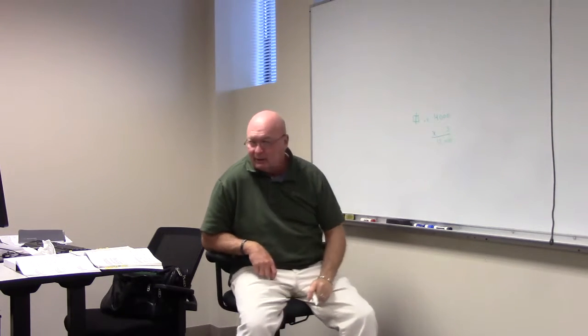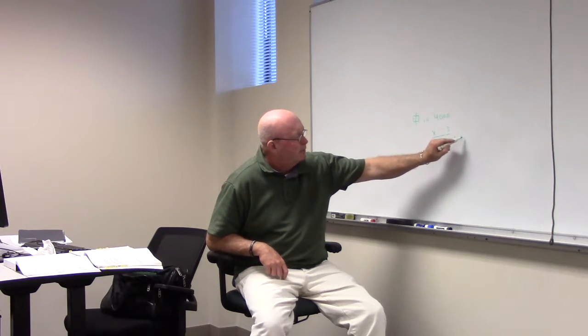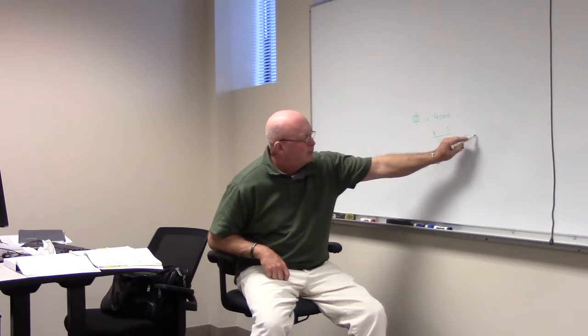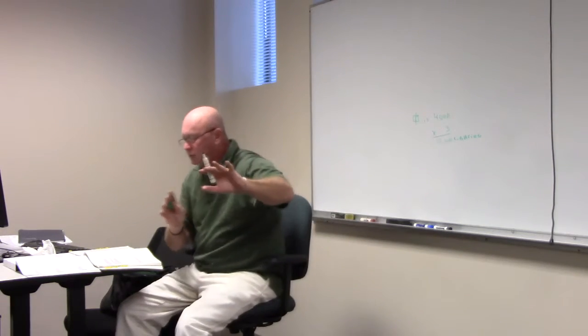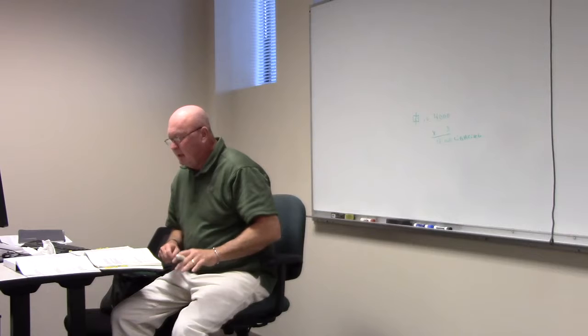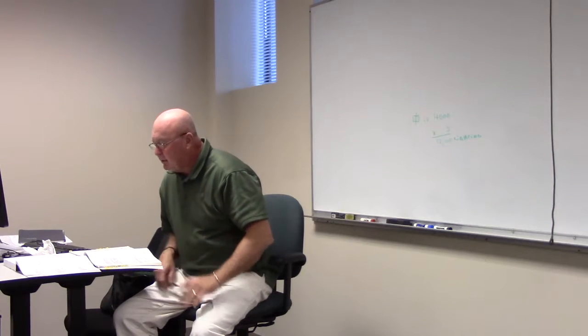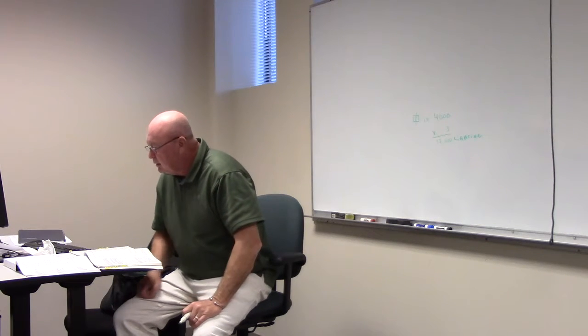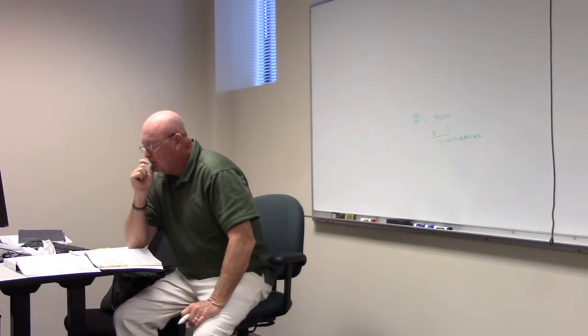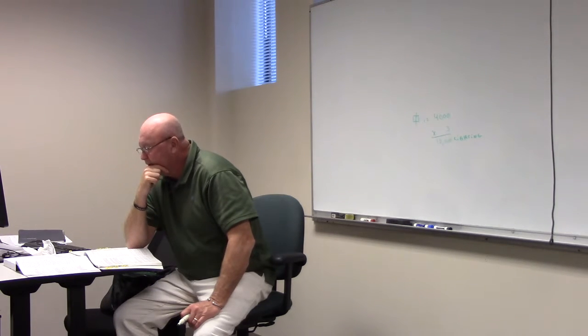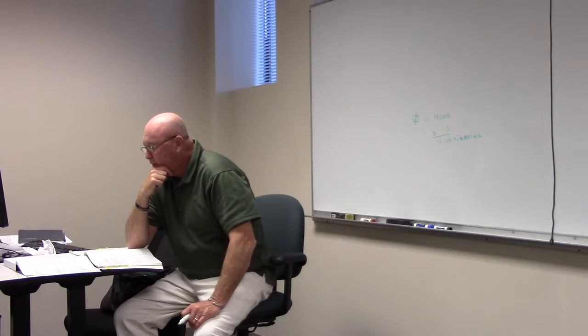That's our lighting. So we're going to write that down and put it to the side. That's our lighting for this store. Now, if we add all those outlets that we had, 4 outlets in the back, you agree? We've got 14 up front is what it says. So that's 18. You with me?